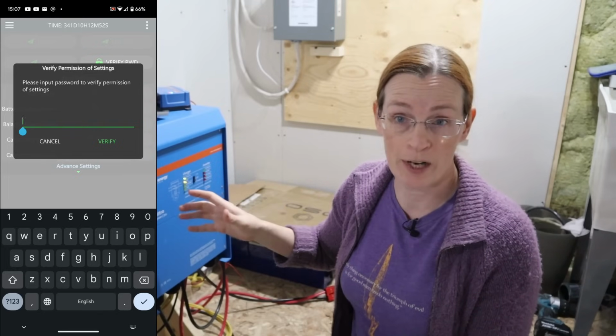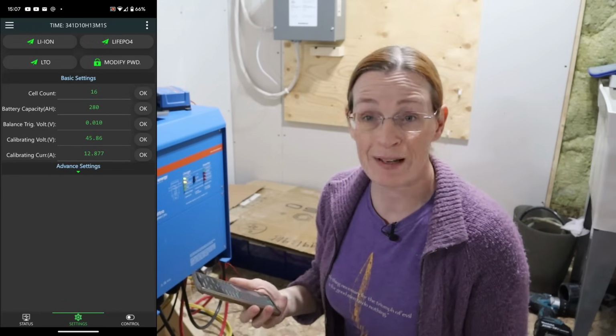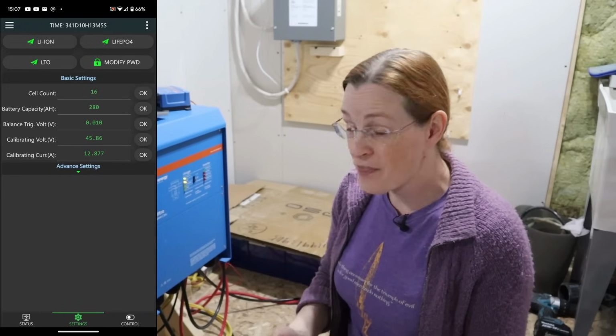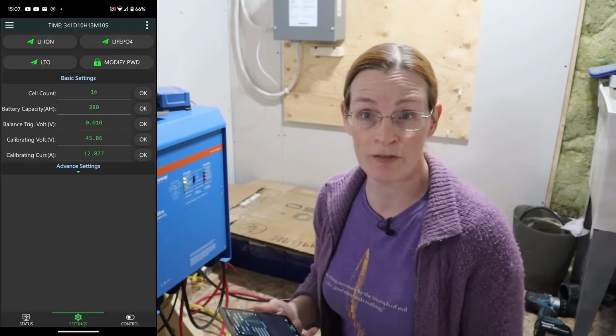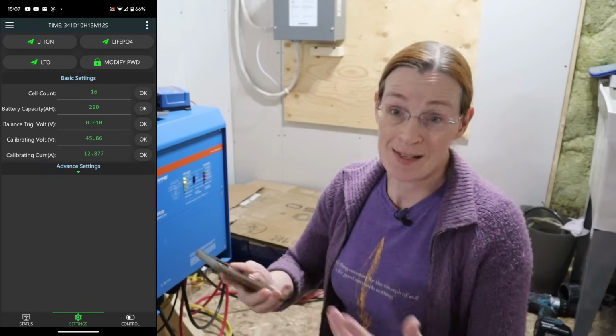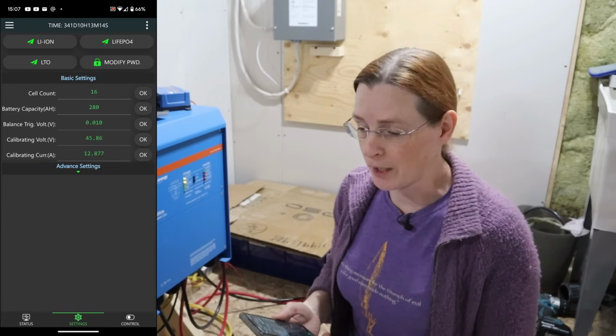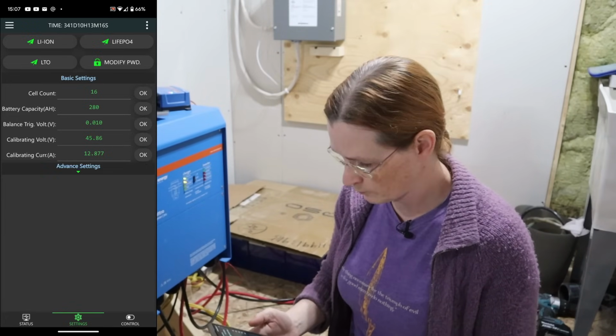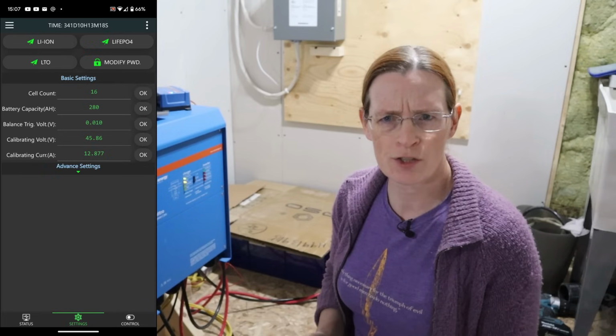So with this current configuration, I got 264 amp hours. If this is the setting that caused it to not reach 280 amp hours, that'll be interesting, because it means setting the batteries to a safe, conservative value sacrifices a certain amount of amp hours per battery, which is good to know, and introduces a whole lot of additional questions.